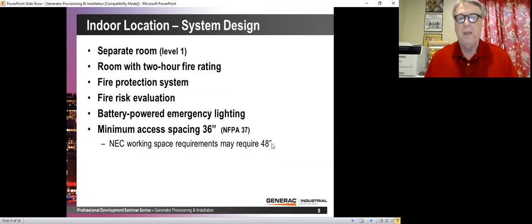And it depends on the NEC. I shouldn't have opened up Pandora's box here, but there's condition 1, 2, and 3 that could require 36, 3 and a half, or 4 feet to any electrical panel. And you can refer to the National Electrical Code for that on clearances. But the generators, the base of the generators need to be 36 inches apart. So this is from the outer end of that U-frame, the base of the generator, to the outer frame of the wall or to another generator.